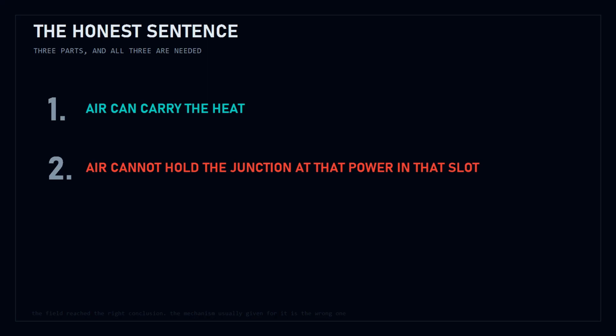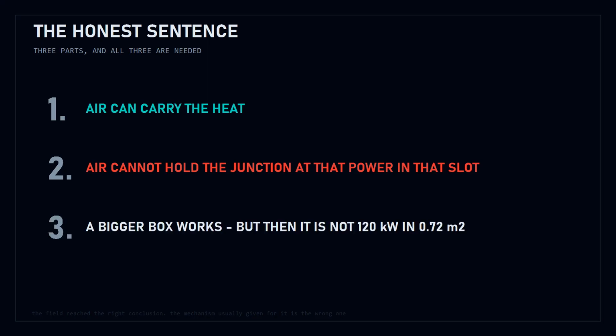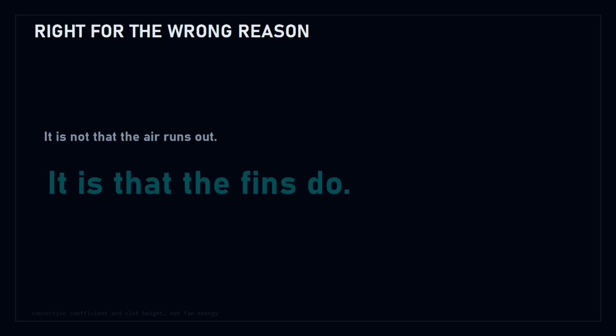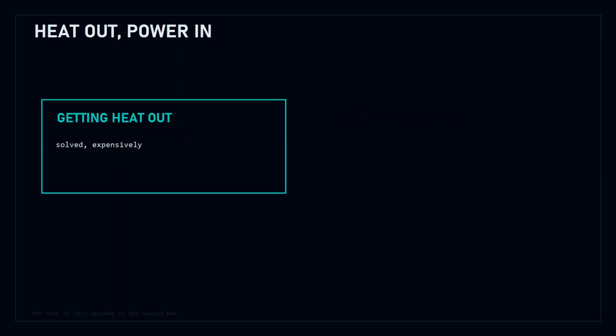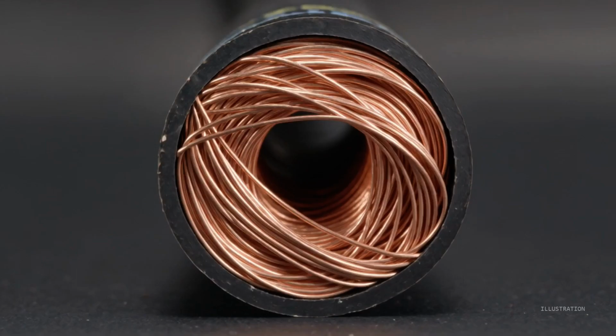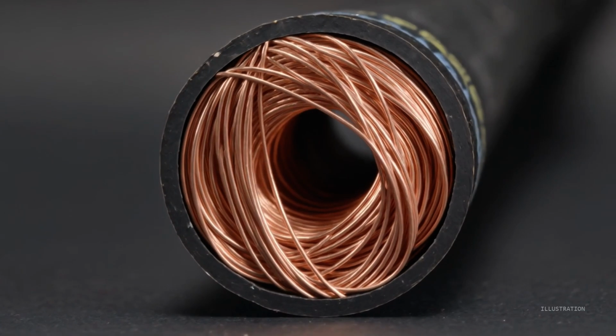Air can carry the heat. Air cannot hold the junction at that power in that slot height. And if you give it a bigger box, air works again, but then it is not 120 kilowatts in 3/4 of a square meter. The field reached the right conclusion through the wrong mechanism. It is not that the air runs out, it is that the fins do. Getting the heat out is solved expensively. Getting the power in is not.